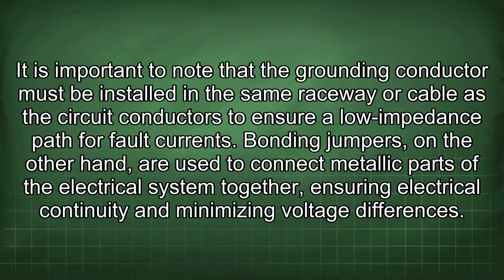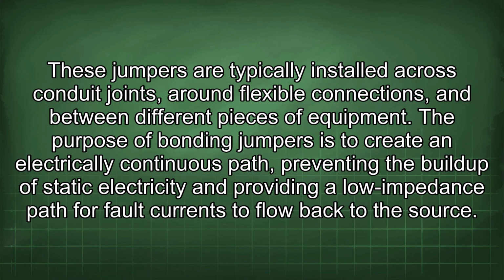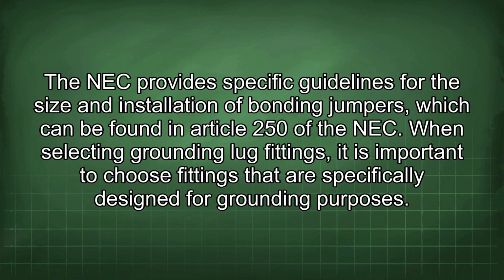Bonding jumpers, on the other hand, are used to connect metallic parts of the electrical system together, ensuring electrical continuity and minimizing voltage differences. These jumpers are typically installed across conduit joints, around flexible connections, and between different pieces of equipment. The purpose of bonding jumpers is to create an electrically continuous path, preventing the buildup of static electricity and providing a low impedance path for fault currents to flow back to the source.